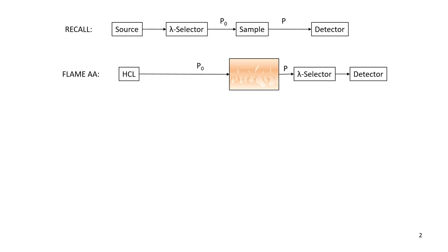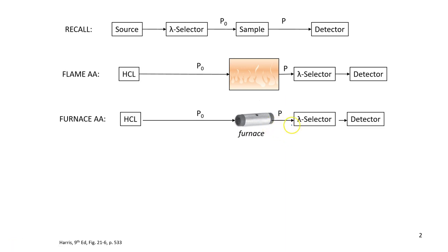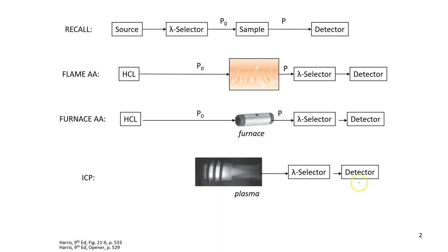The furnace AA is also very similar. It also uses a hollow cathode lamp. The sample is found inside of this small furnace. It's only about an inch long. And absorbance is measured. You still have these components. And then finally, in ICP, there is a plasma. Notice that something's missing here. We don't have a light source because the plasma is a little bit different. But you still have the wavelength selector and a detector.